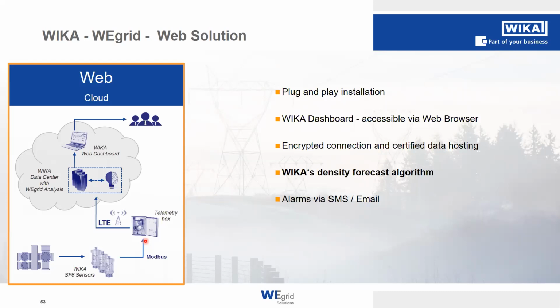And on this data hosting, we are running a WEGrid dashboard, which we will take a look at later as well, which is accessible via any web browser. Furthermore, we have a density forecast algorithm that is enabling the customer, the operator, to have a forecast for the density in the future, especially if they have leakages in the GIS. They can see when they need to refill the compartment. We will take a quick look at that later on. And also this dashboard is providing a function to provide alarms to the operator via SMS or email, for example, once the values have dropped below the given thresholds.